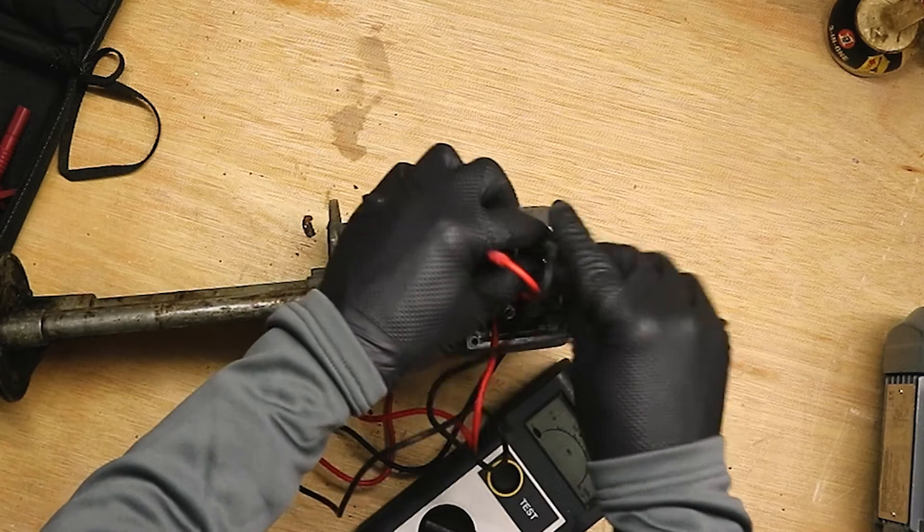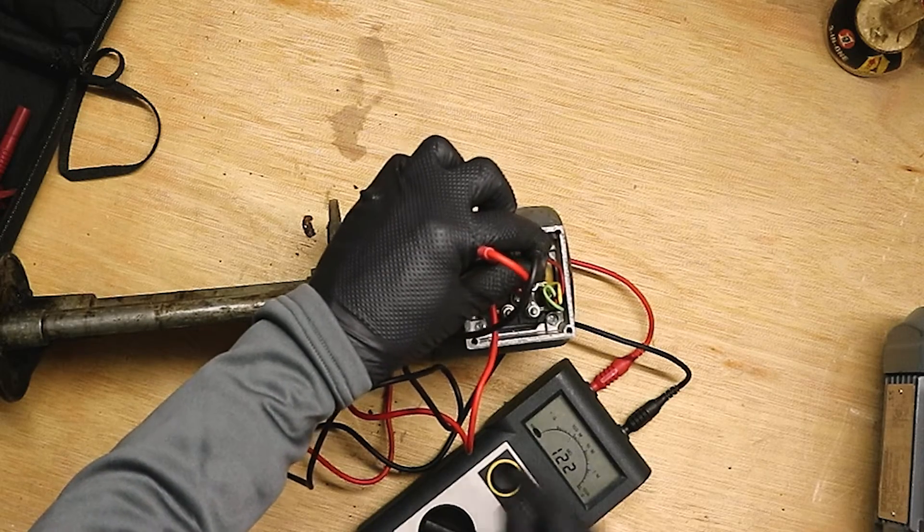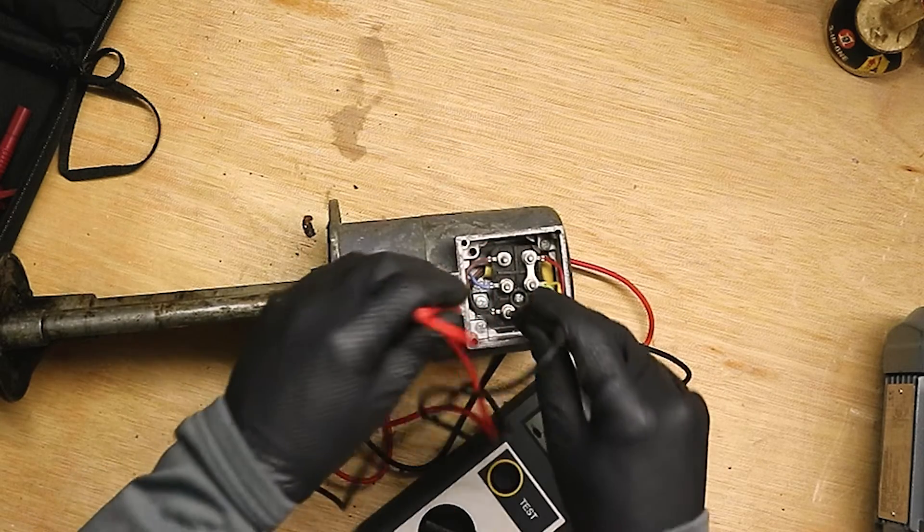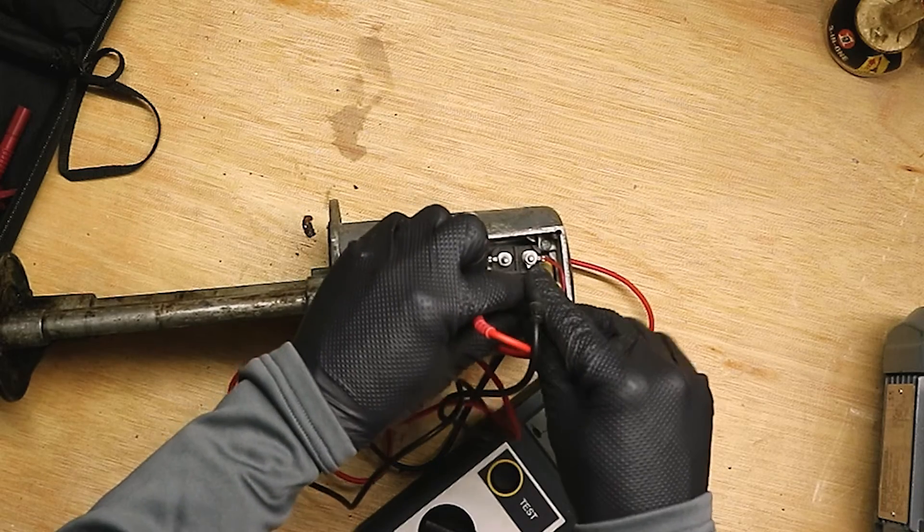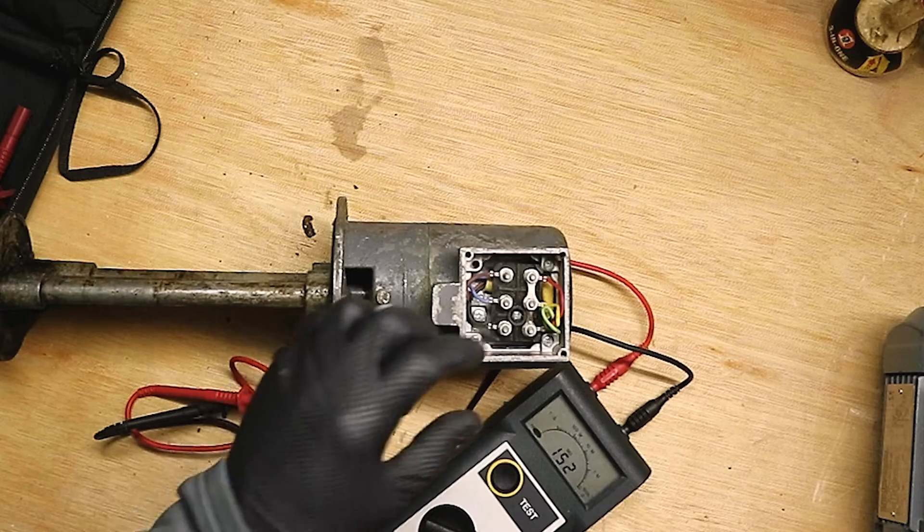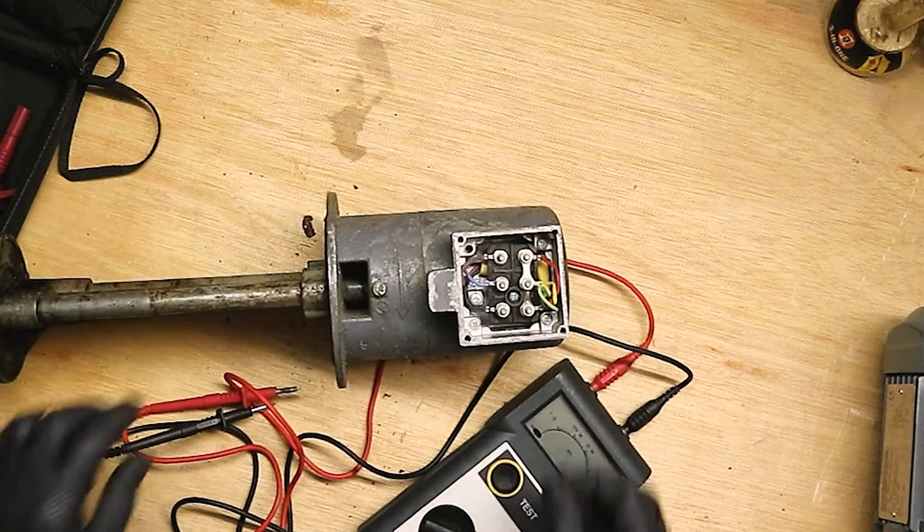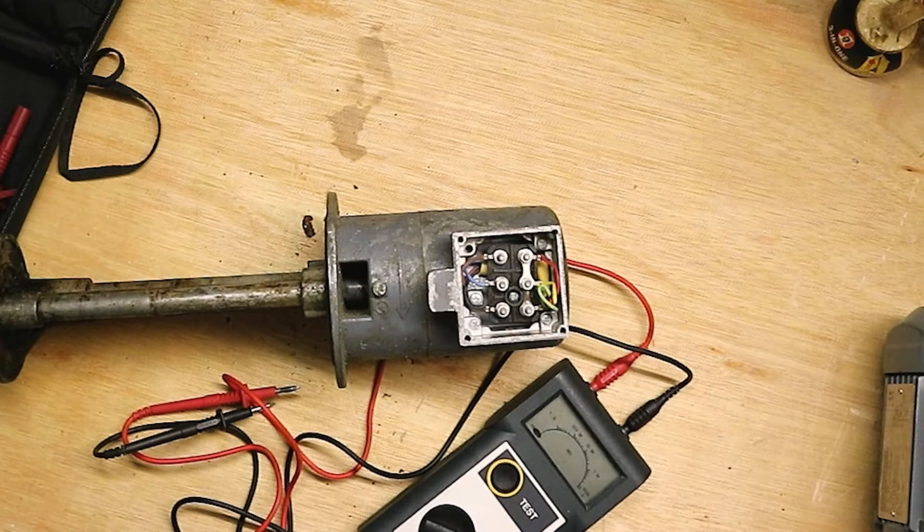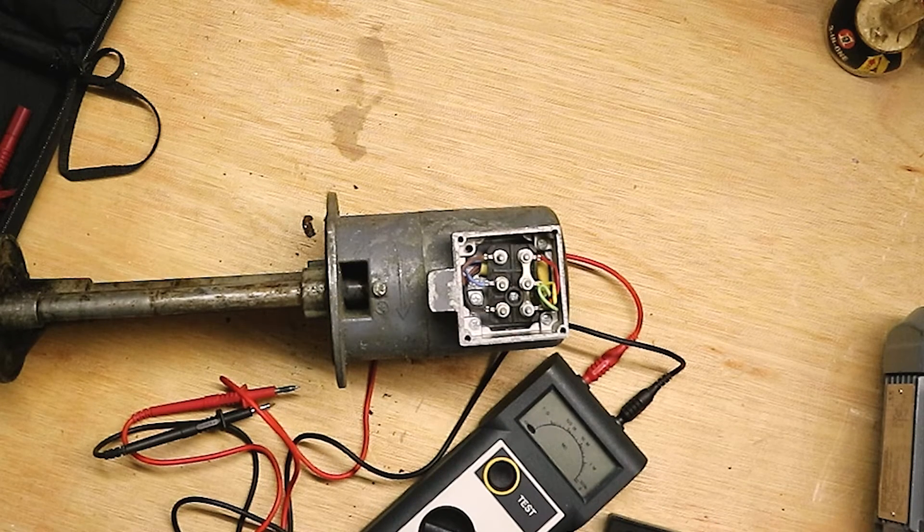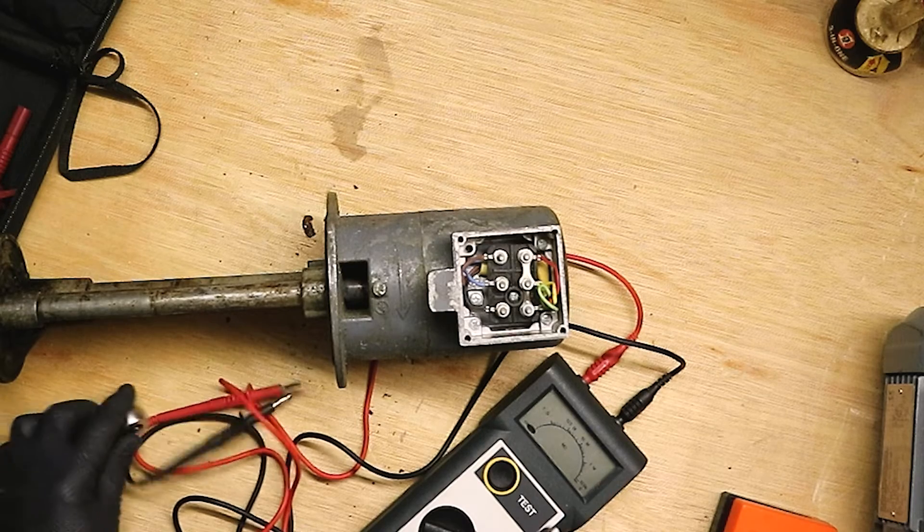So we'll just do a quick test, 500 volts, 121 mega ohms, so that's not too bad. Test it to ground, that's not too bad either. So what we're going to want to do now is test each winding, low ohms reading on each winding to try and understand what the problem was. This motor was tripping out the motor overload, so there is a problem with it.